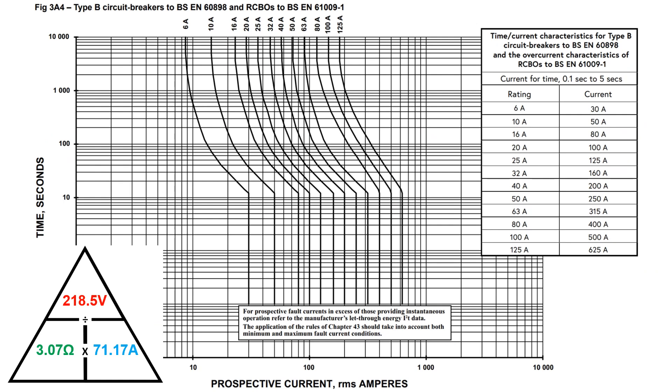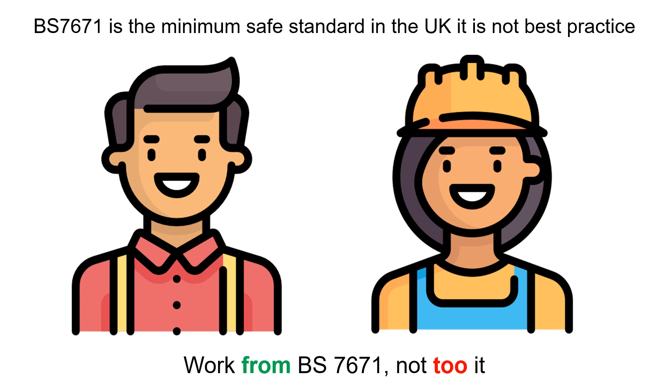looking in BS7671, Appendix 3, at the time-current characteristics of overcurrent protective devices, figure 3A4 gives the characteristics for MCBs and RCBOs. We can now see that if we plot a line from around 70 amps, it will now take around 15 seconds to operate the protective device. That is 3 times longer than it should be. So as you can see, it does not actually make sense to avoid carrying out R1 plus RN testing on ring circuits. But please consider this as you continue with your career as an electrician, because you can make a difference within the industry.